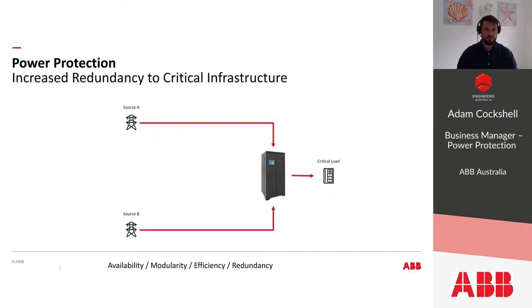In order to increase the redundancy and reliability of a critical power infrastructure, you can add an STS, or a static transfer switch. Typical design incorporates two separate supplies. So obviously your source 1 or source A and your source 2 or source B, feeding a preferred and an alternate source of the STS. Our Cyberex DSTS, or digital STS, continuously monitors power quality on both the preferred and alternate sources and transfers accordingly in the event that the power quality deteriorates beyond the user-defined thresholds.